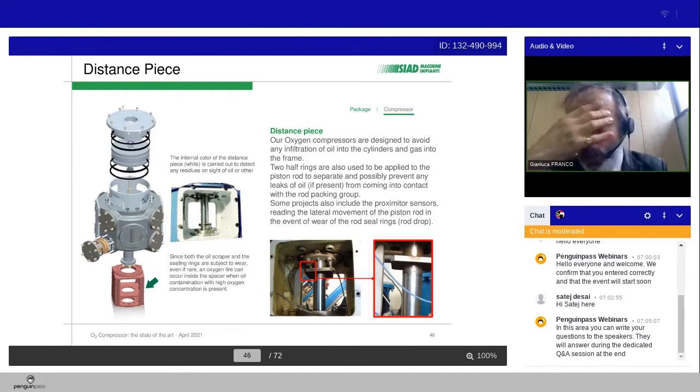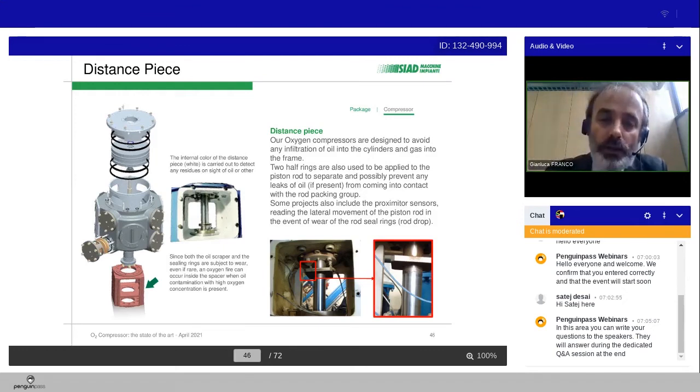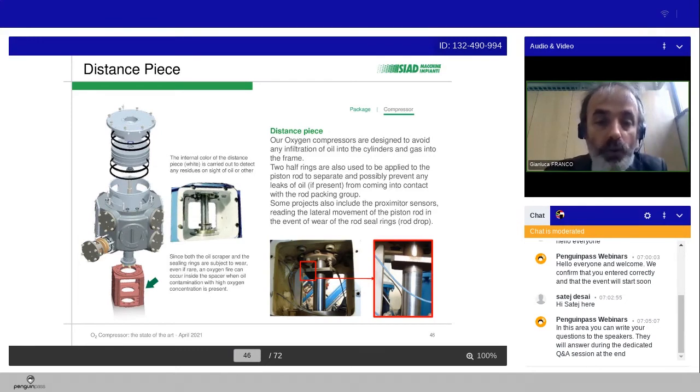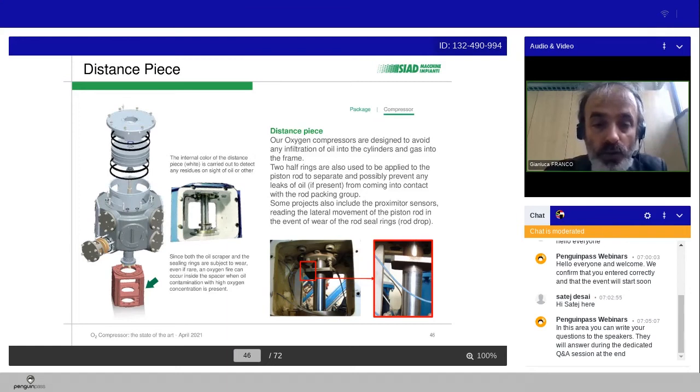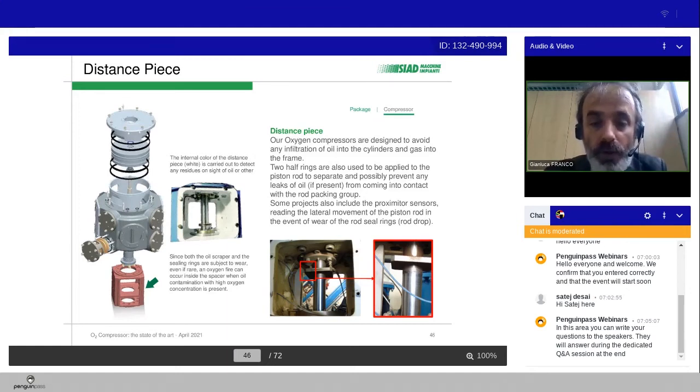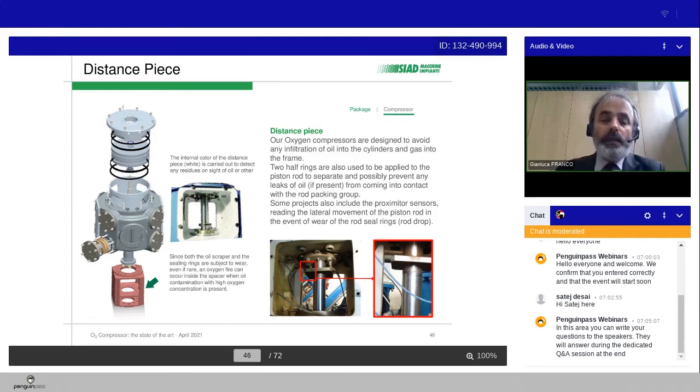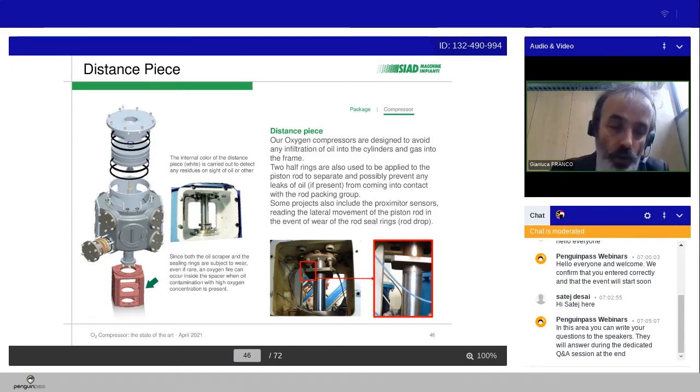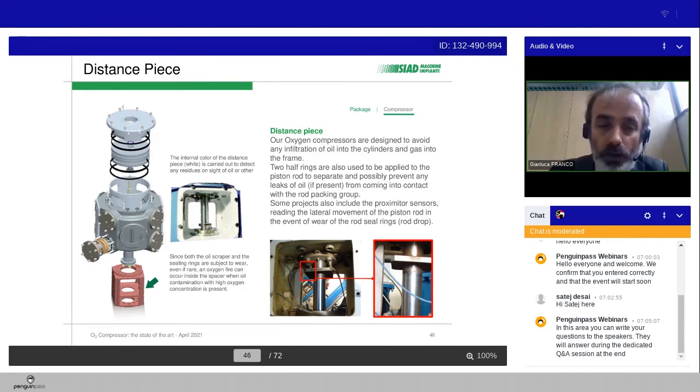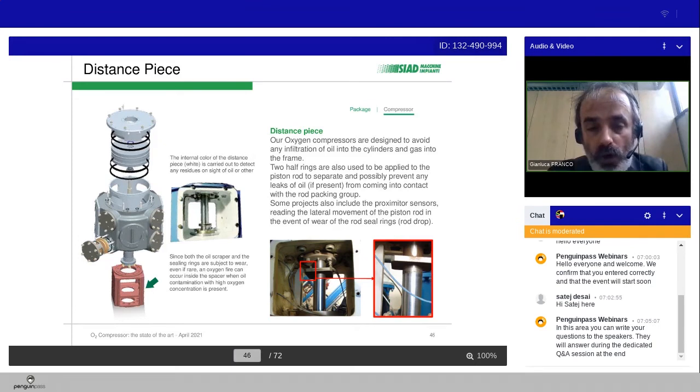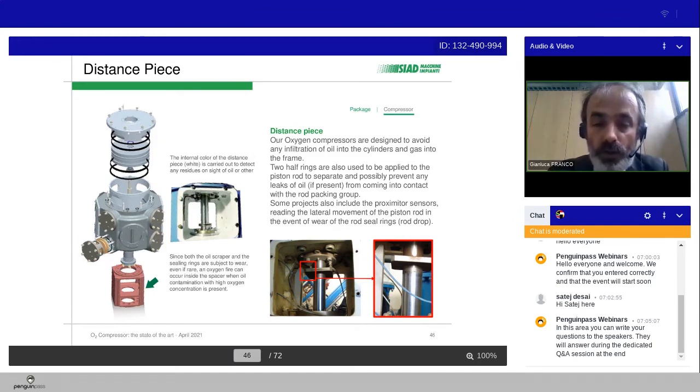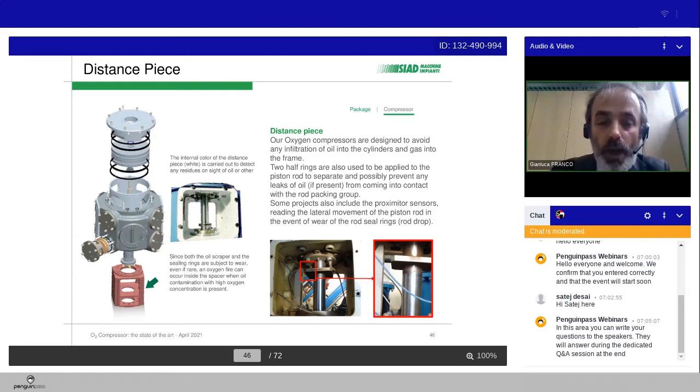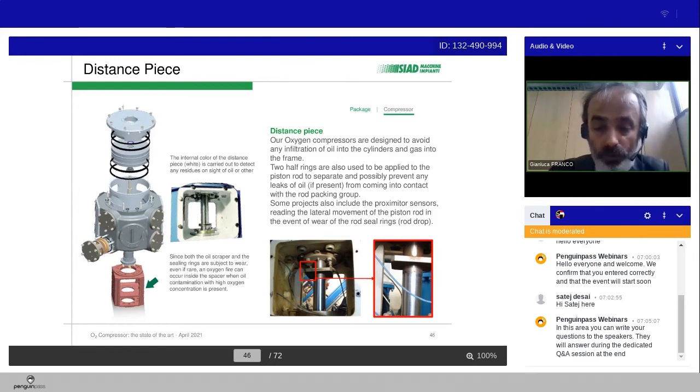We have an additional protection system, because our oxygen compressors are designed to avoid any infiltration of oil into the cylinder and gas into the frame. We have two half rings used to be applied to the piston rod to separate and possibly prevent any leaks of oil, if present, from coming to contact with the rod packing groups. In some machines, if required, or if we consider the customer and the design of the group, we can also include the proximity sensors, so the rod drop system, reading the lateral movement of the piston rod in the event of the wear of the rod packing group rings.